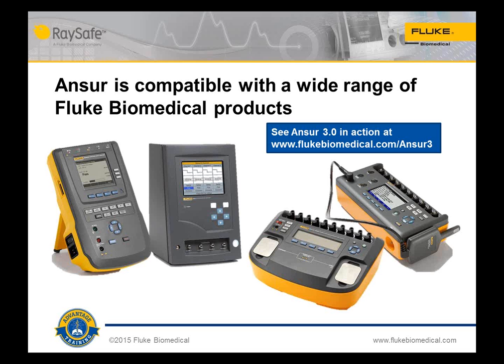Ansur is compatible with a wide range of Fluke Biomedical products. For example, ESA 615 electrical safety analyzer and our other electrical safety analyzers, the IDA 5 infusion device analyzer, the Impulse 7000 defibrillator analyzer, the ProSim 8 patient simulator, the VT Plus, HF, VT 305, and VT Mobile gas flow and pressure analyzers, including when they're used for ventilator testing, the QA-ES II electrosurgical unit analyzer, and many of our legacy medical device analyzers, including those that are MedTester compatible.